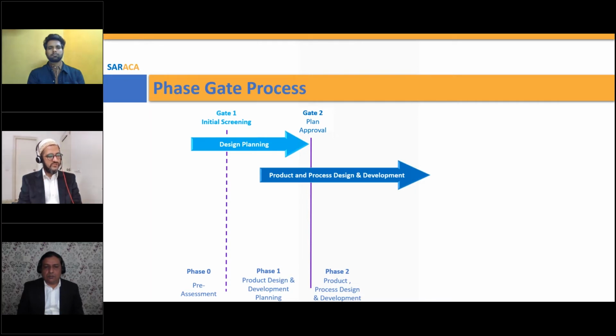In this phase, formally, you'll start by compiling your user requirements in terms of a marketing specification or user requirement specification. It will be a document in which you have all the requirements in terms of functionality, ergonomics, safety, regulatory, labeling, and packaging. All points you'll have to list down in this particular phase. Those are your design input.